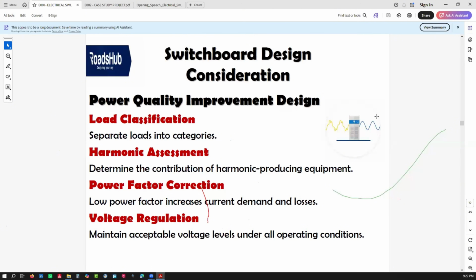If you want to know what affects your system, you need to identify load classifications. Are they linear loads or non-linear loads? What's the harmonic assessment? What is causing a lot of harmonics, like variable frequency drives? You need to put detuned reactors in power factor correction. For voltage regulation, we use AVR and AVS, automatic voltage regulators and automatic voltage stabilizers, to make sure our systems work perfectly.